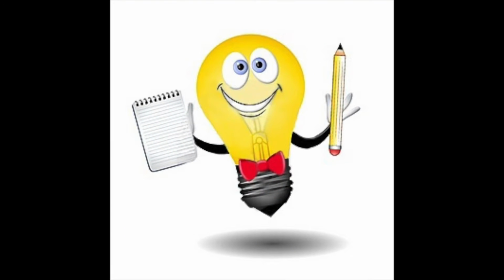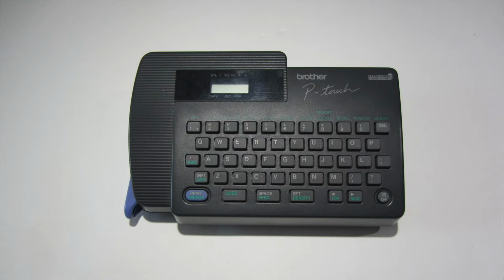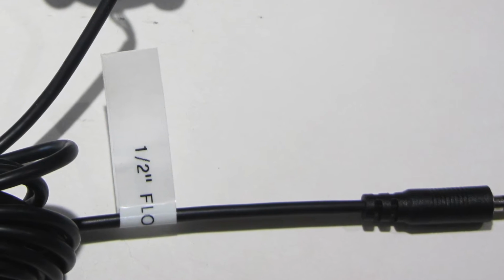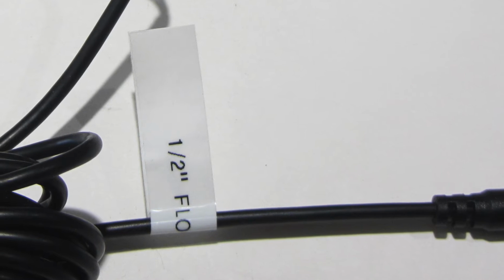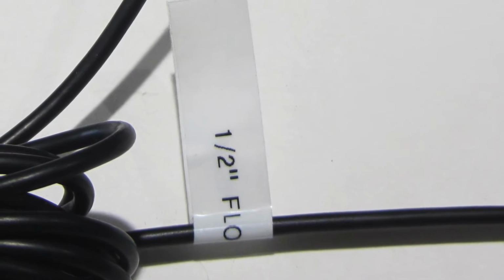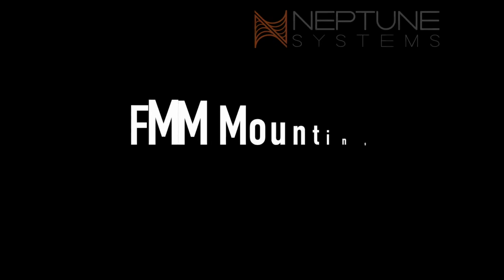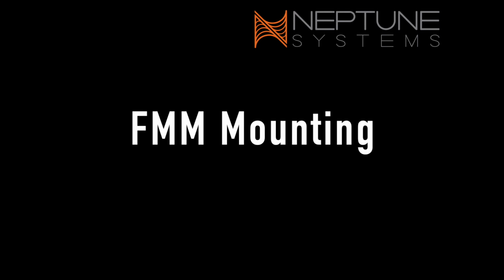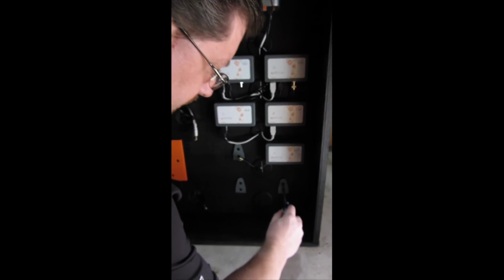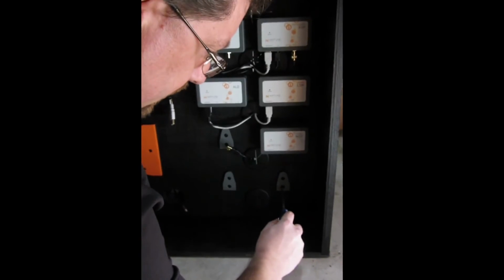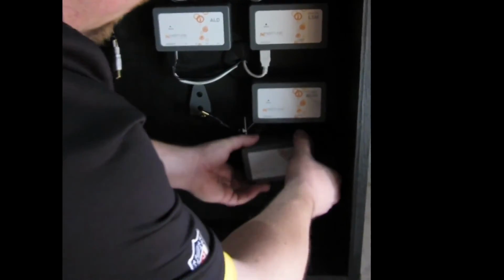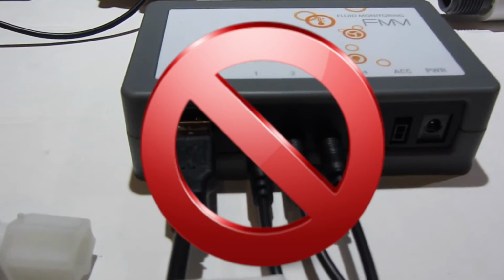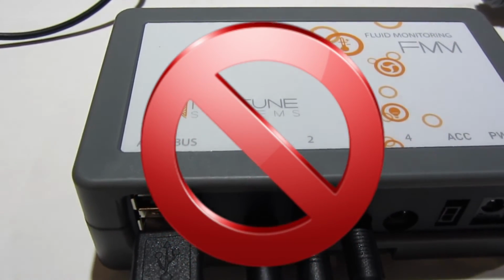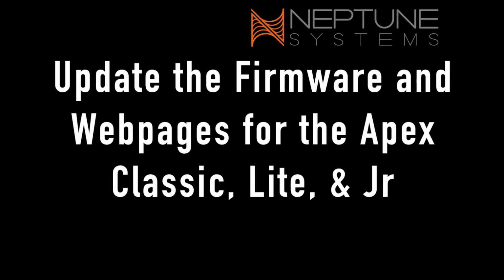At this point, it would be helpful to take the time to label the end of the flow sensor cables with the correct size of each specific flow sensor. This will be beneficial when setting up the FMM and for any troubleshooting needed down the road. Mount the FMM with your other modules, and make sure that the flow sensor cables can reach to the module. Please do not attach the sensors or the Aquabus cable to the FMM yet.